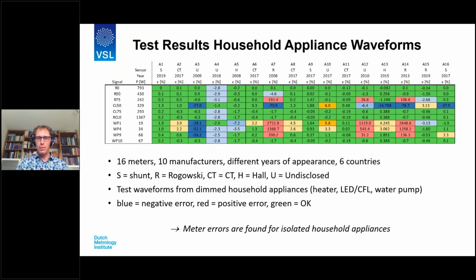Now I don't expect you to read all the numbers, but the colors speak for themselves. Green here means okay within 2%. Blue means that it's more than 10% less energy recorded, which is good for you. And red means more than 10% too much, which is bad for you. You can actually see that several meters show enormous errors, either with energy readings too high or too low. And roughly speaking, we can see that the relative errors are largest for low power signals, where the power is concentrated in a very sharp peak. And in the most extreme cases, you can see that this leads to errors of up to several thousands of percent.